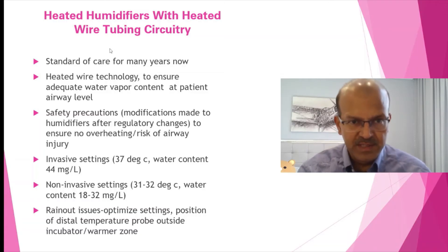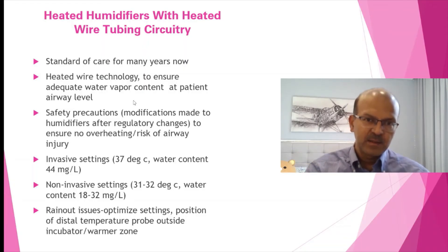The heated humidifiers with heated wire tubing circuitry have been the standard of care for many years. By using the heater wire, you are maintaining the water vapor content at the patient airway level as well as the temperature. Even if it drops on the way, the heater wire heats up the gas and maintains it. We mentioned the safety regulation.